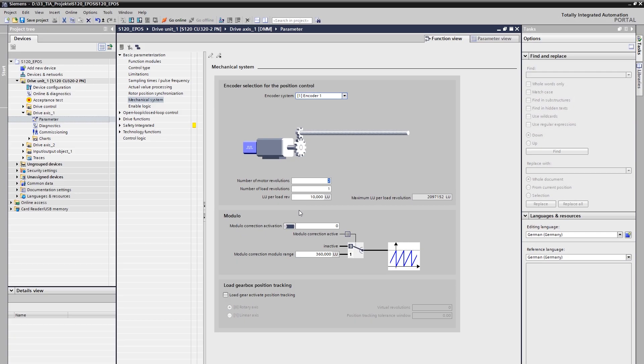In the third step, we have to define the relation between the physical units and the neutral, so-called length unit or shortly LU. This independent unit LU gives the user the flexibility to convert one load revolution into any measurement. The higher the number of length units per load revolution is defined, the higher the resolution of the actual position value preparation. The height of the input of LUs is limited by the maximum LU per load revolution. This limitation results from the encoder configuration and the gear ratio.